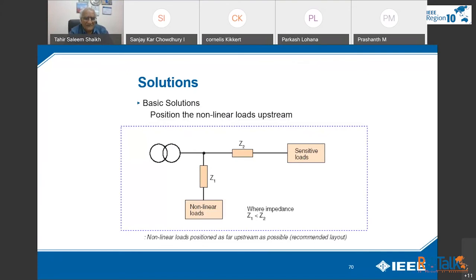The basic solution is to position the non-linear loads upstream, remotely from the source. This figure gives you Z1, the impedance for non-linear loads, and Z2 for the sensitive loads. So we have to place them. You have to decide with the harmonic spectrum, what solution is the best, and how much to invest in this. That is your own decision. So this is one solution: you position your non-linear loads upstream.